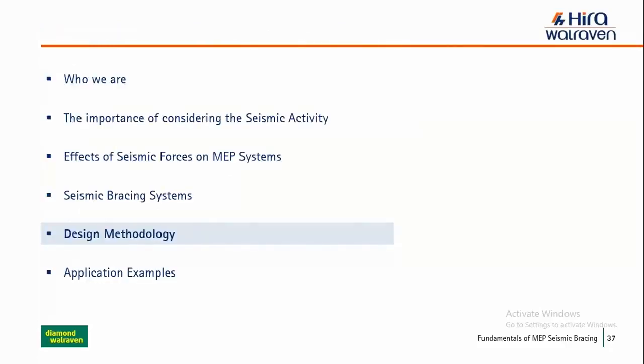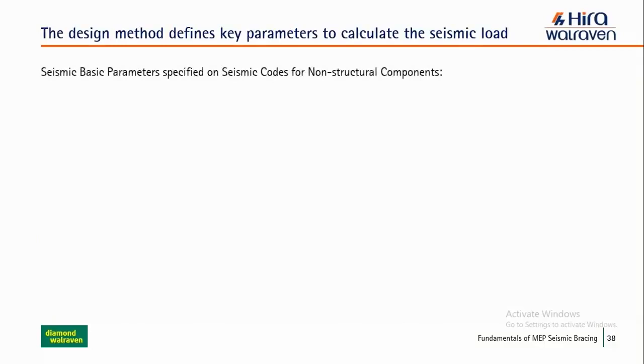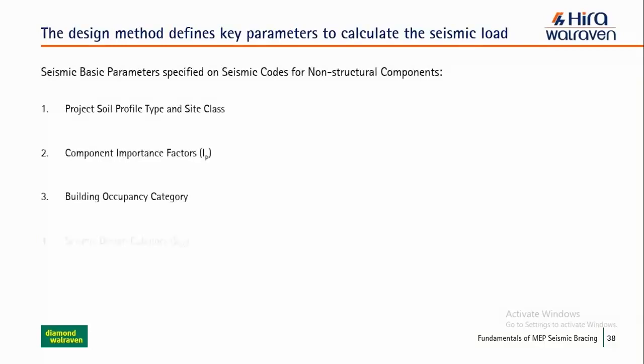So in the seismic bracing system, we have discussed lateral sway, rigid and cable bracing systems both, and the advantages of the cable bracing system over the rigid bracing system. Then we discussed different types of bracing: lateral brace, longitudinal brace, sway brace, and what standards shall be applicable for the horizontal run and for the vertical risers. Now we will discuss design methodologies to design any system for the non-structural.